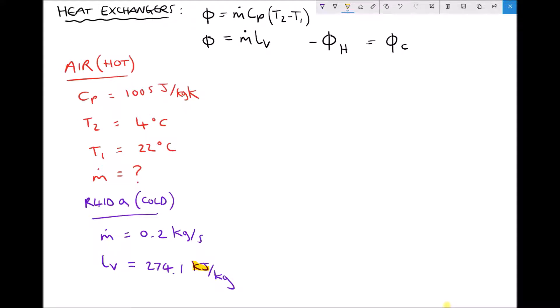On the right hand side we have our heat transfer formula: the rate of heat lost by the hot fluid (negative) equals the rate of heat gained by the cold fluid (positive). We have two formulas for rate of heat transfer. The first is mass flow rate times specific heat capacity times change in temperature. Since the refrigerant temperature doesn't change, that formula wouldn't be applicable for it. Instead, for the refrigerant we use mass flow rate times latent heat of vaporization — a change in state rather than a change in temperature.